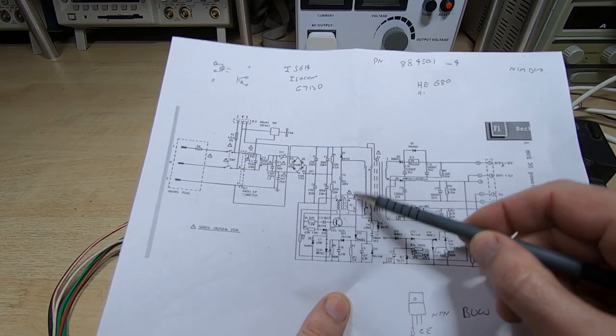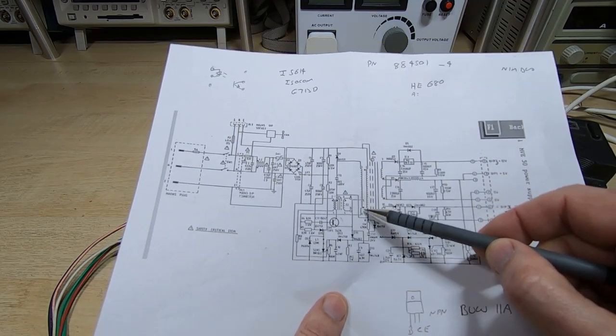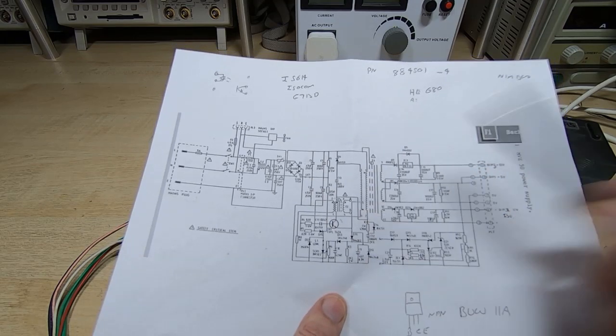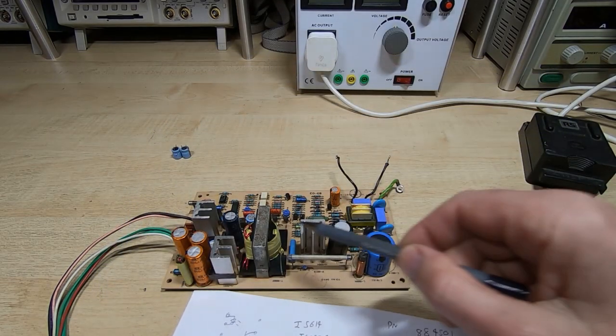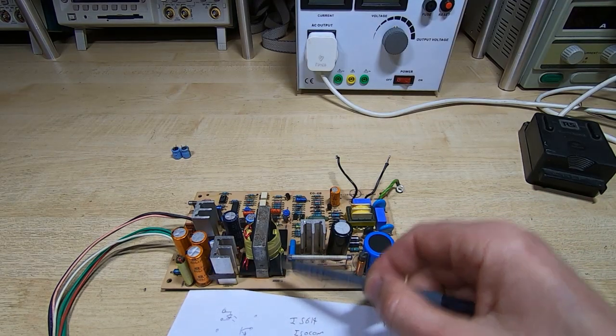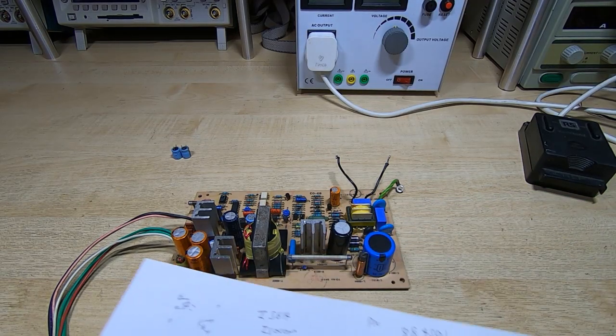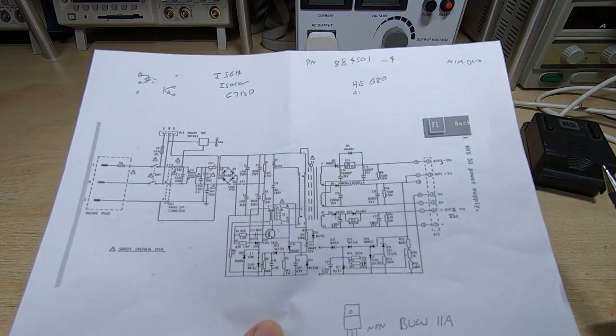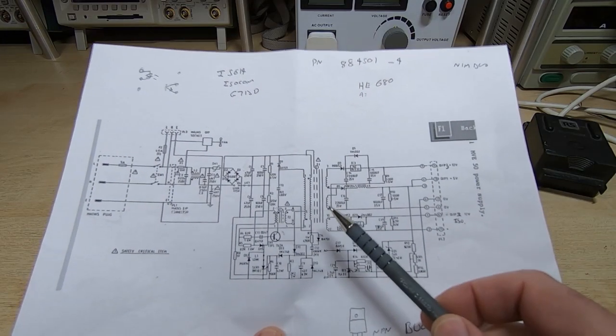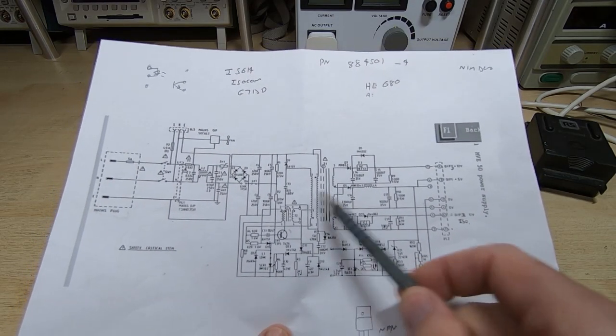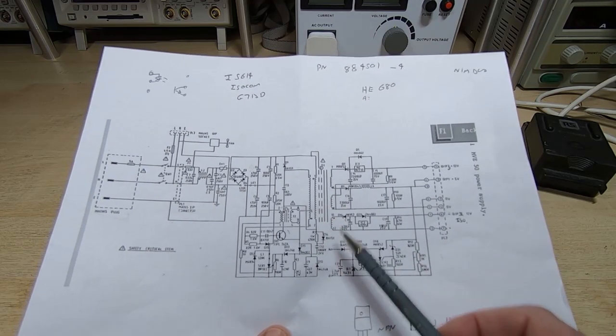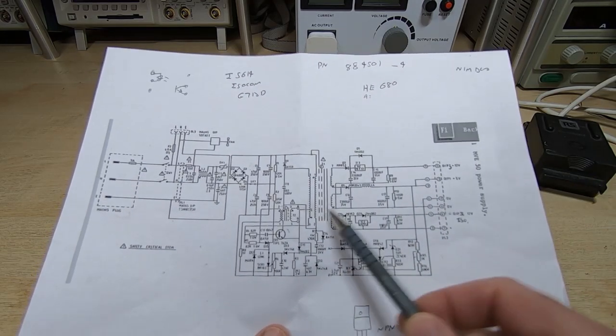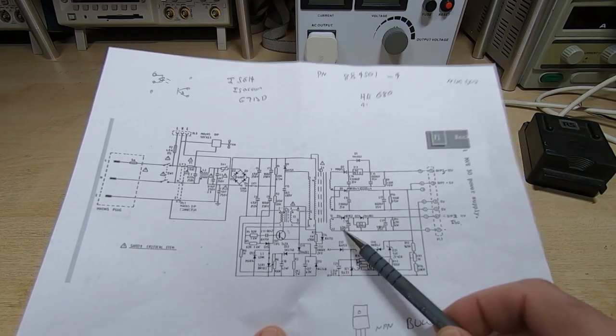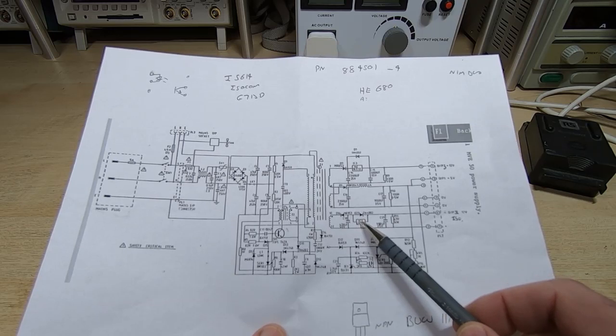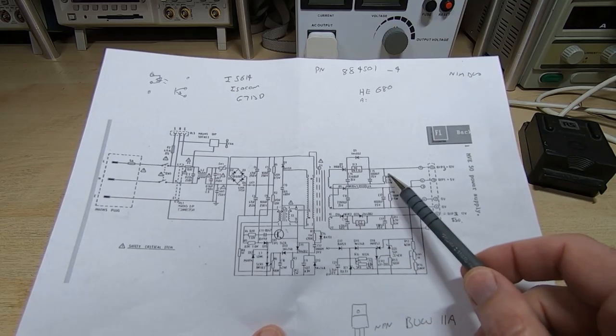And it does that by essentially connecting the full supply across one of the windings. Now, I did check as part of the initial fault finding that the windings were all intact, or they seem to read something sensible anyway, so it doesn't guarantee the transformer's okay, but it's a fairly good sign. They normally go open circuit if there's an issue, or you get shorting between the input and output side, and again I checked for that and it was fine. A bit of leakage, but nothing major. I've checked these output stages as far as I can, so I know there is nothing dead short on the output.